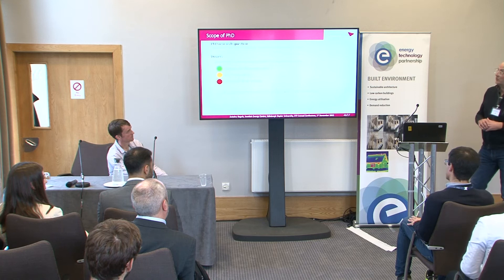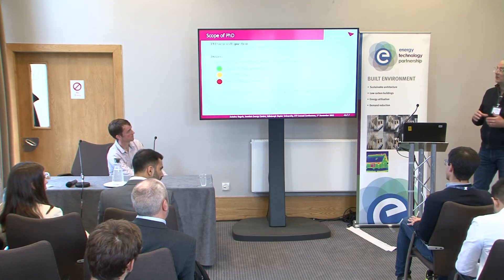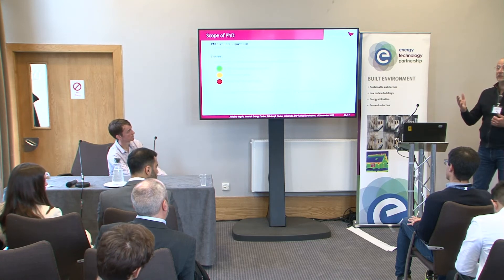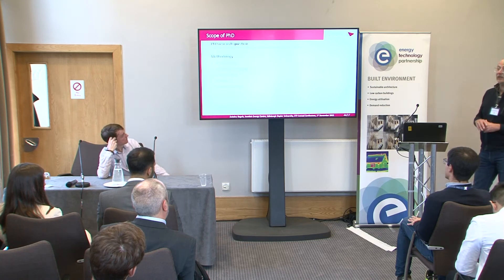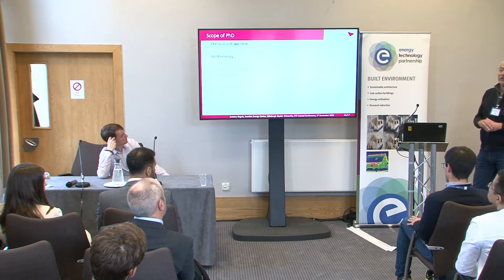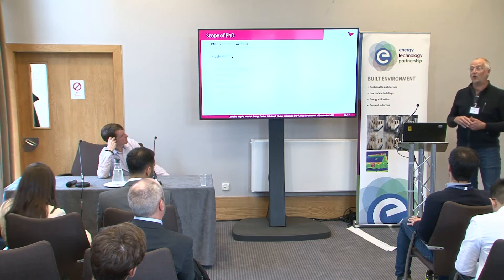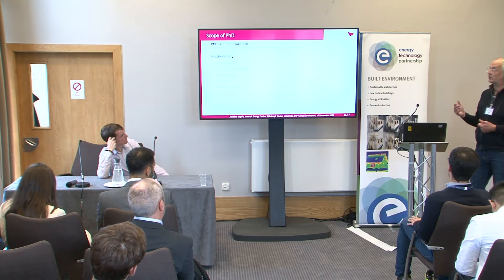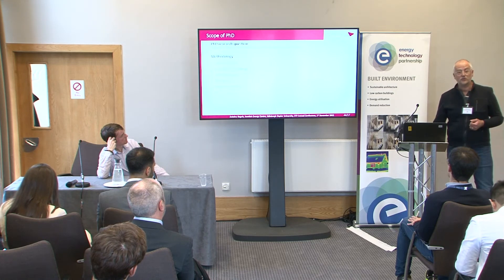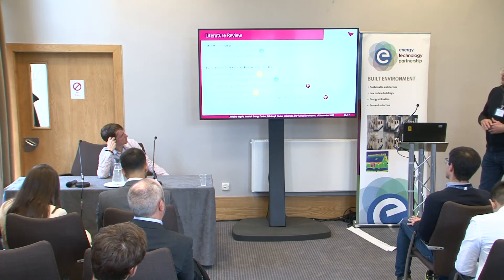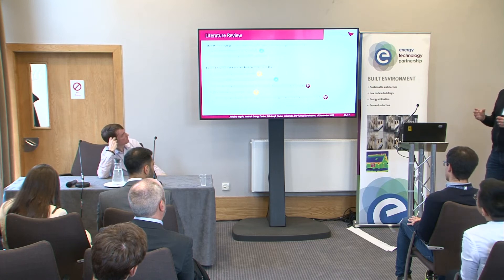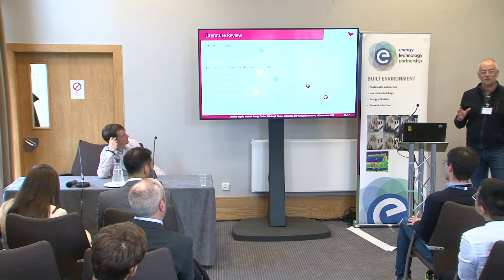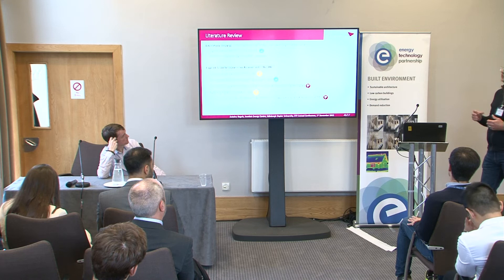It could also support government's desire for buildings to be low temperature ready — could we develop a sort of certification to say this building is low temperature ready? The methodology was to look at what's happening elsewhere in Denmark and Sweden, focus on Scottish public buildings because public buildings will be the first to connect, and look at the performance gap. The three criteria are: the performance gap of the building, oversizing of the heating system, and operation of the system — including whether to continue night setback or move towards continuous heating. In Denmark, they consider their building stock has a nascent readiness and are now tracking faults, considering it ready to connect to low temperature. Can we export those conclusions to the UK?